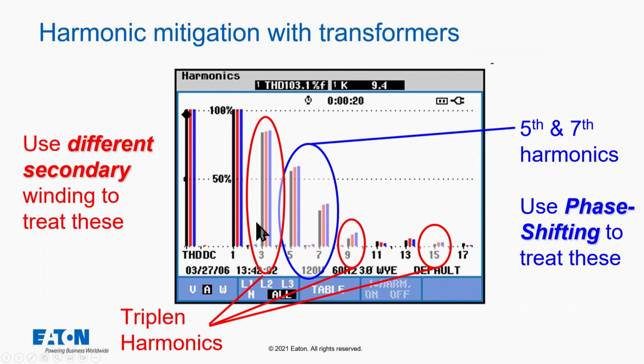Okay? And then if you look at all the different parts of that spectrum, we have the fundamental, which of course is doing the work, and we're not going to eliminate that. We could get rid of the thirds or recirculate the thirds back to the loads. We could do that with a delta-Y or a delta-zigzag. Again, the benefit of the delta-zigzag is you don't get the heating losses in the primary winding. Fifth and seventh can be eliminated or minimized with phase shifting by taking combinations of transformers. And you can even do that with the 11th and 13th, 17th and 19th. So you can make 6-pulse systems go into 12-pulse, 18-pulse, 24-pulse.